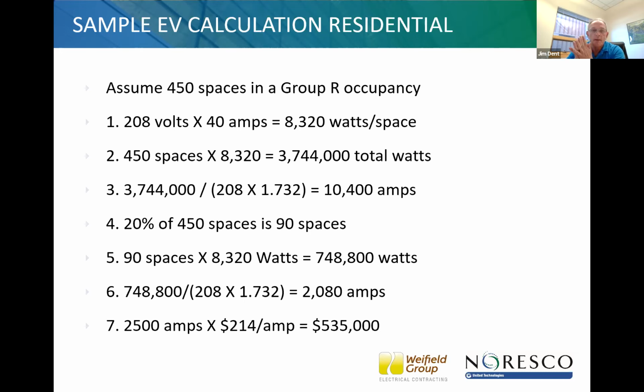So assume a group R occupancy with 450 parking spaces. What I did here was I took two Weifield projects, two high-rise, both of which had around 450 parking spaces. And on each project, I took the cost of the switchgear and the cost of the feeders, and I added those two numbers together and divided it by the total amperage of the facility to come up with the cost per amp. So that's how I got to where we got in this calculation.